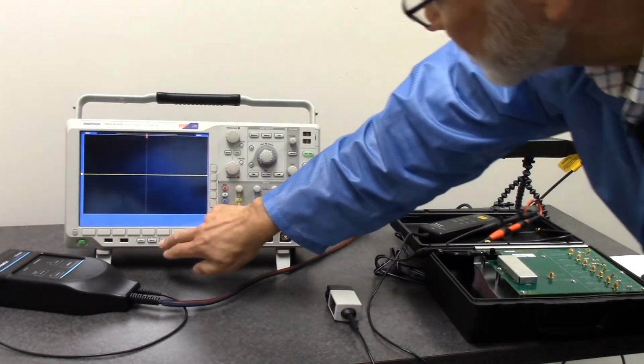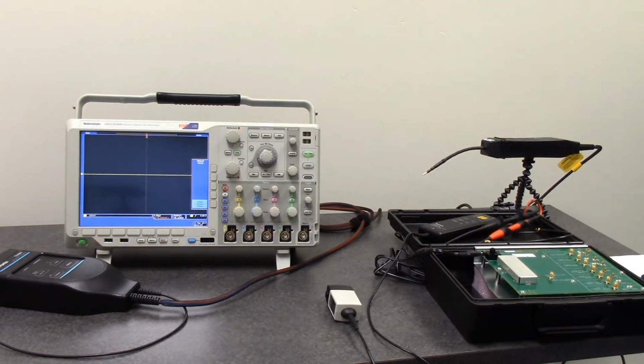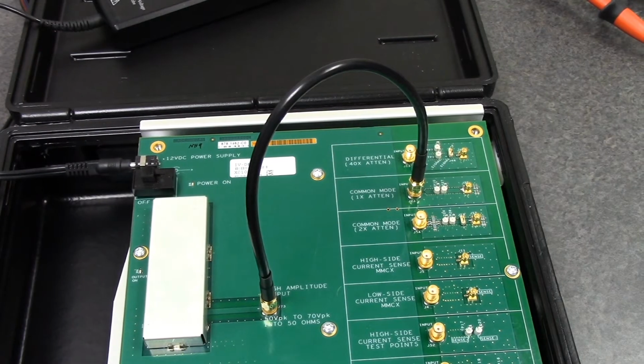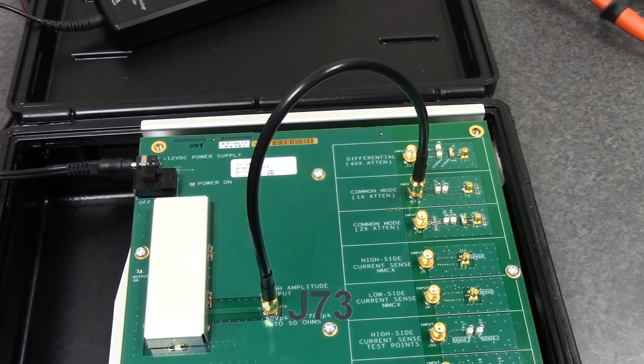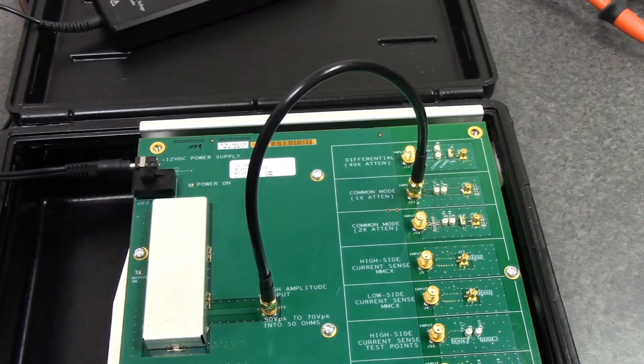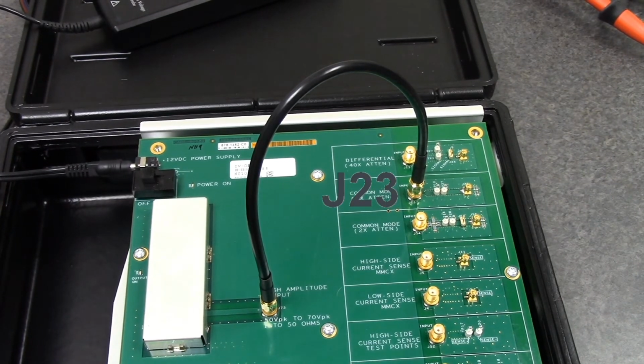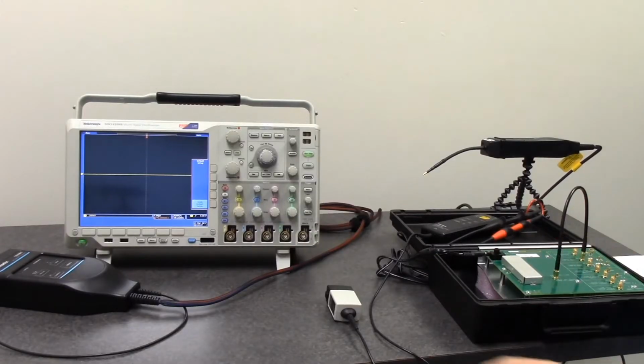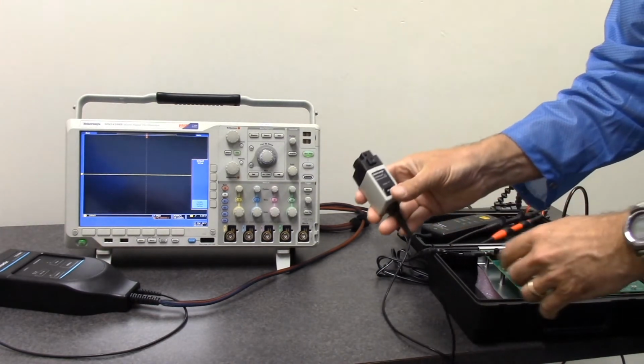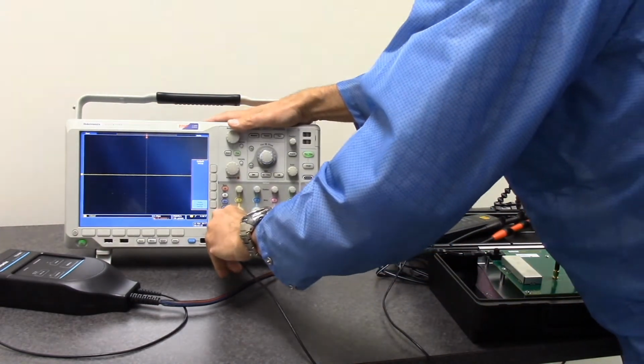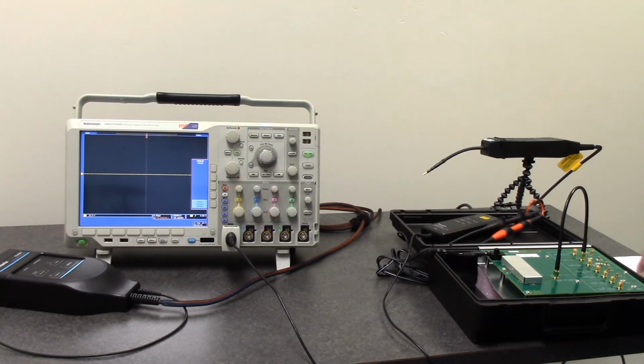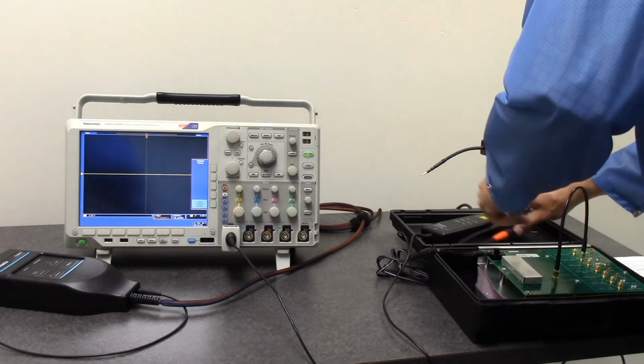Press Default Setup on the scope. Now make sure that the power supply is turned off to the demo board, and connect the SMA cable from the high amplitude output connector J73 to the common mode 1x attenuation connector J23. Now we're going to connect the TMDP-0200 to channel 1 of the scope. Set the TMDP-0200 to the 75 volt range. Connect the probe tips together and perform the auto zero operation on the scope.